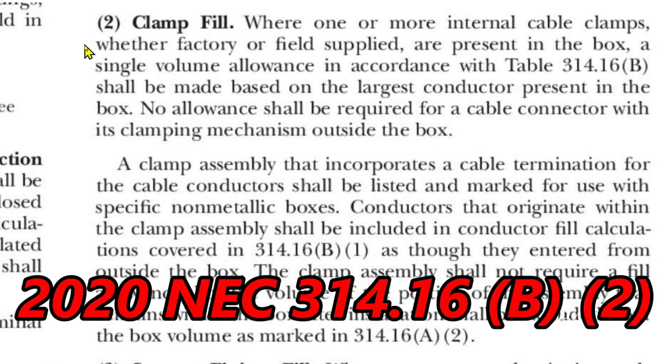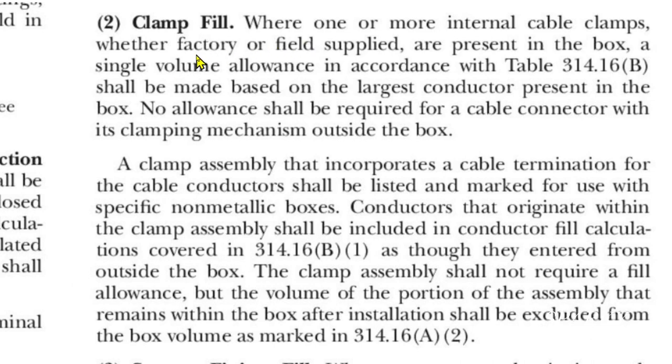Here we are at 2020 NEC 314.16B2 clamp fill. Where one or more internal cable clamps, whether factory or field supplied, are present in the box. A single volume allowance in accordance with table 314.16B shall be made based on the largest conductor present in the box.